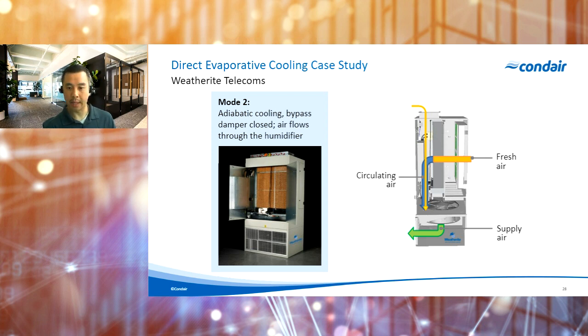In this mode, the bypass damper is closed. We force all of the fresh air through the evaporative module. We cool and humidify on the discharge side. And then we do have the option here to mix that with recirculating air as well. And then that is supplied to the space.